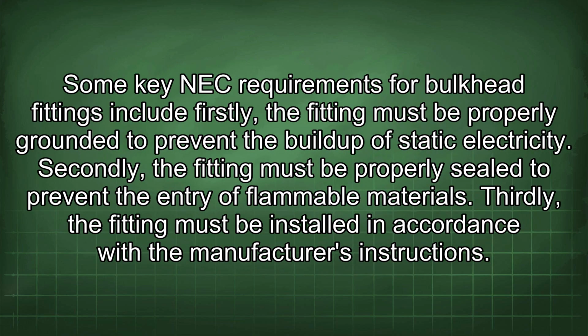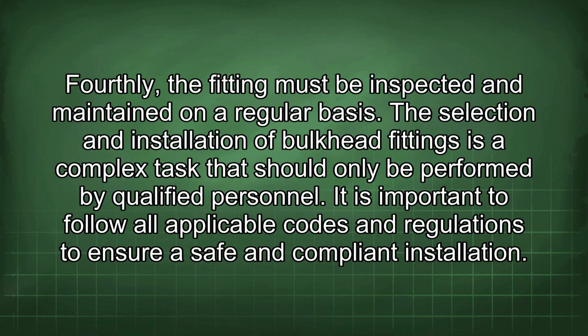Some key NEC requirements for bulkhead fittings include: firstly, the fitting must be properly grounded to prevent the buildup of static electricity. Secondly, the fitting must be properly sealed to prevent the entry of flammable materials. Thirdly, the fitting must be installed in accordance with the manufacturer's instructions. Fourthly, the fitting must be inspected and maintained on a regular basis. The selection and installation of bulkhead fittings is a complex task that should only be performed by qualified personnel. It is important to follow all applicable codes and regulations to ensure a safe and compliant installation.